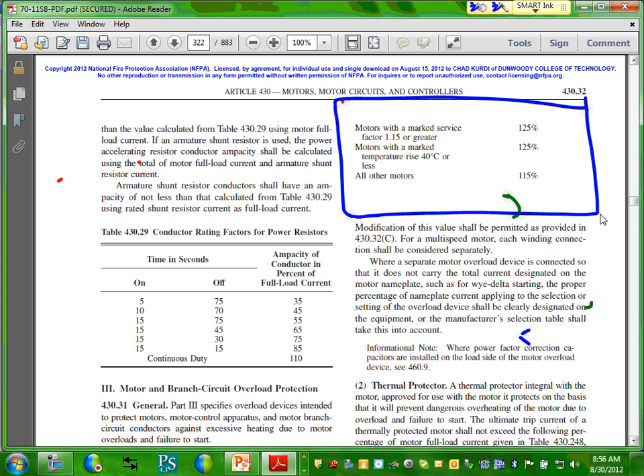So let's look at this. If your motor has a standard service factor of 1.15 or greater, did we say anything about the service factor for this motor? Do we have any idea what the service factor is? No. So we can't use this one. Motors with the marked temperature rise of this amount, 1.25. All other motors that you have no clue what they are, what's your multiplier? 1.15. So what's your default? 1.15 unless they tell you information.